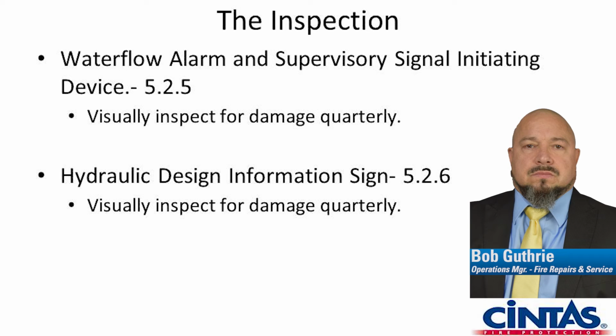Our inspectors, we just want them to record that it's there and look at the pressures, the static pressure, meaning no water flowing. That information was recorded on the calc plate, and we can compare that to what is actually there now. And then if it has a large gap in between, say the calc plate says we had 100 pounds of water pressure, but when we're doing our inspection, there's only 80 pounds. We can show that as a recommendation, and that's something we ask inspectors to do, is write that as a recommendation that there needs to be some further investigation to determine if the sprinkler system is still effective for the use of containing a fire.